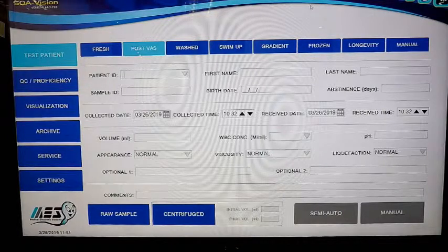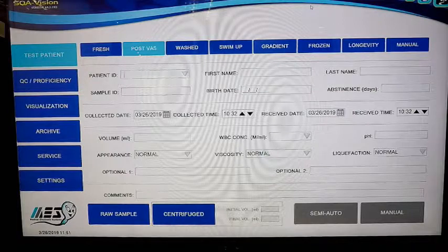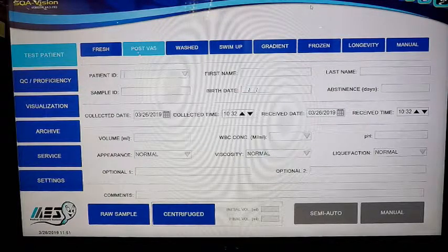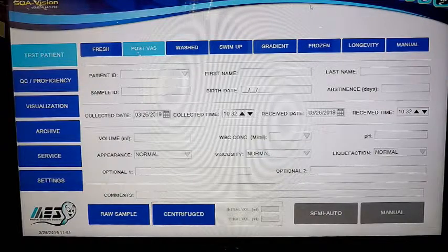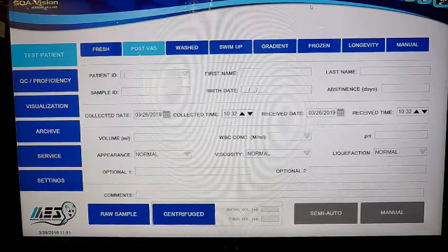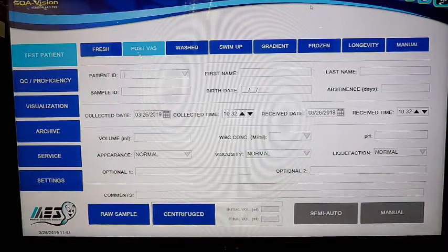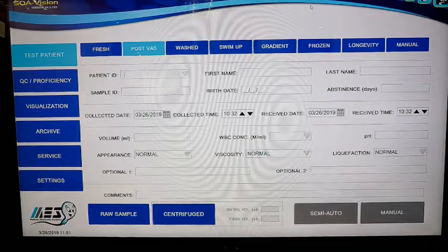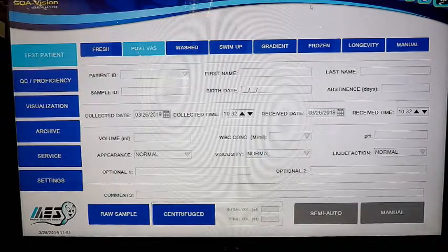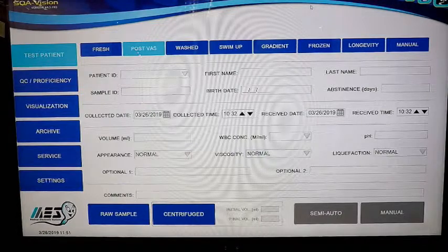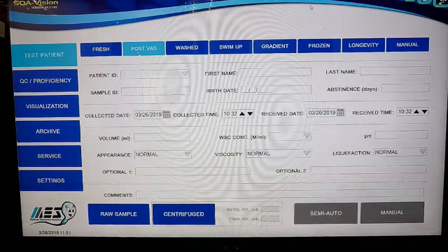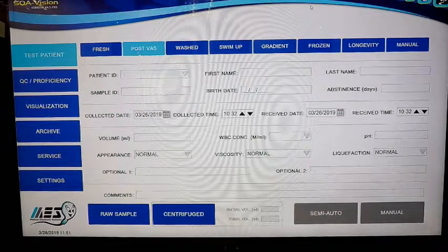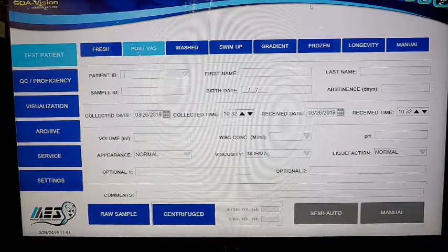There are several different ways and workflows to use our instrument for this type of test. There are options based on which criteria you're using as far as the WHO manual recommendations you're following and your own internal procedures. There's a semi-automated mode that uses our automated technology and a full manual mode where you're just using lab slides. I'll touch on all the different options and provide our recommendation for the best way to use the system.